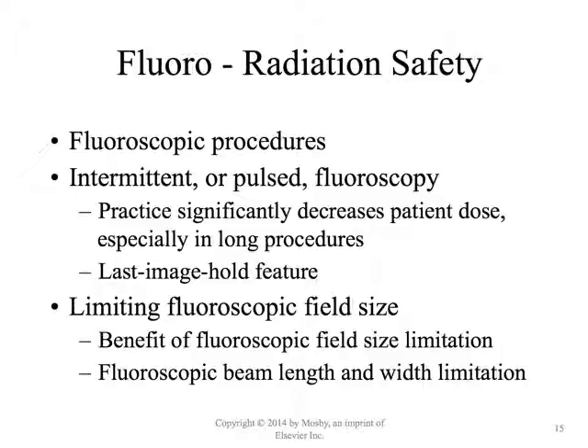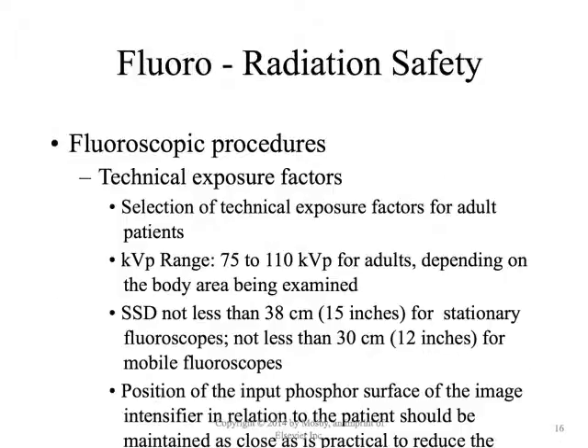We want to decrease field size whenever possible. Time spent decreasing field size is good. It will actually clearly enhance your image, and it will reduce the patient's exposure as well as your exposure, because you're the one having to stand out there. And the weird thing about fluoroscopes is the primary area of backscatter radiation is going to be on the side of the X-ray tube. You would think that if you're standing on the side opposite the X-ray tube, where the X-ray tube is pointed right at you, that you would be getting the largest amount of dose. But that's not the case. With fluoroscope, it's the side of the X-ray tube that gets the primary dose, and that's largely from backscatter radiation from the patient.